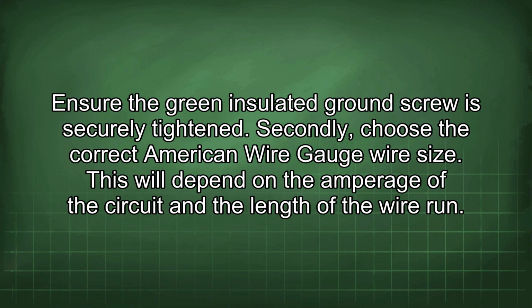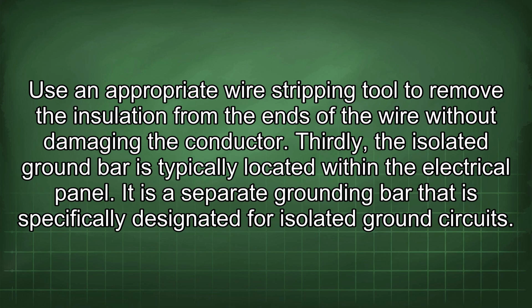Secondly, choose the correct American wire gauge wire size. This will depend on the amperage of the circuit and the length of the wire run. Use an appropriate wire stripping tool to remove the insulation from the ends of the wire without damaging the conductor.